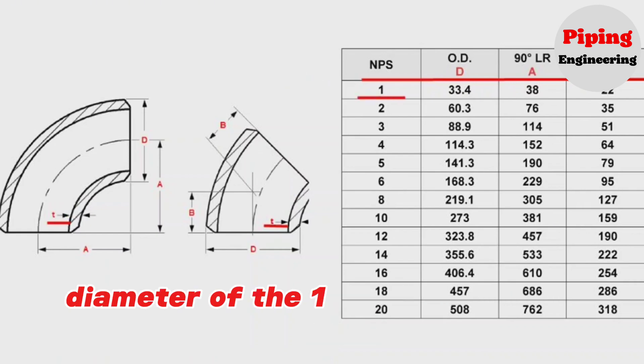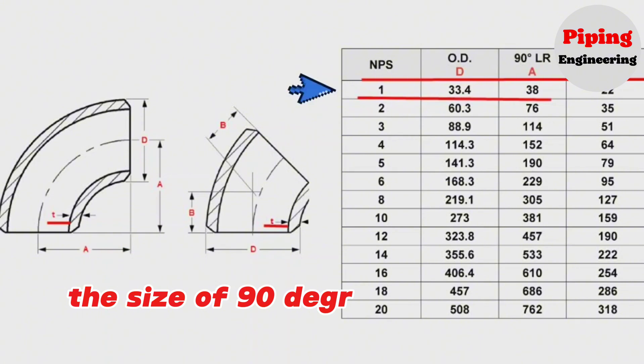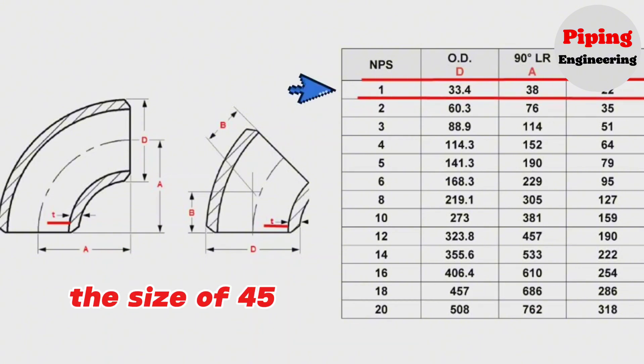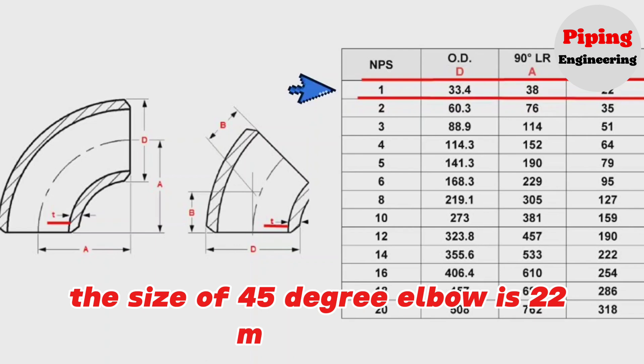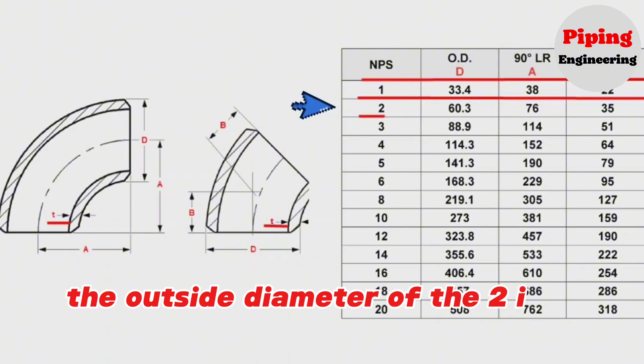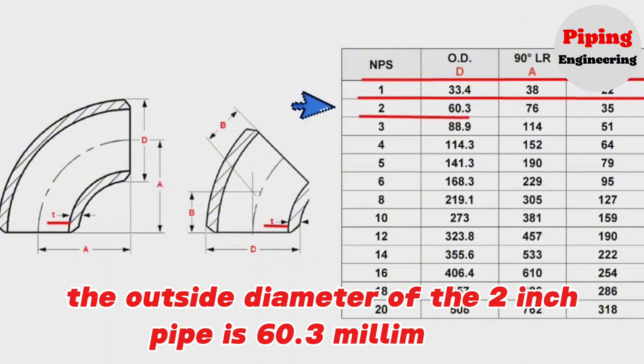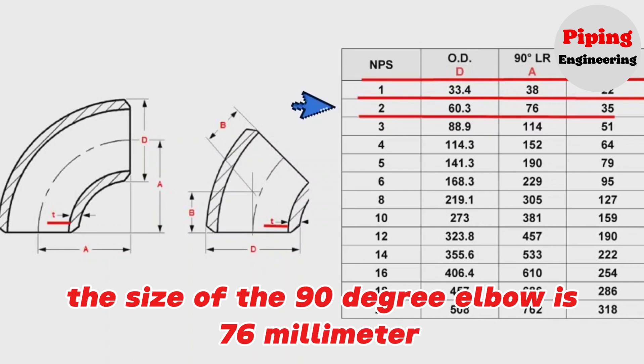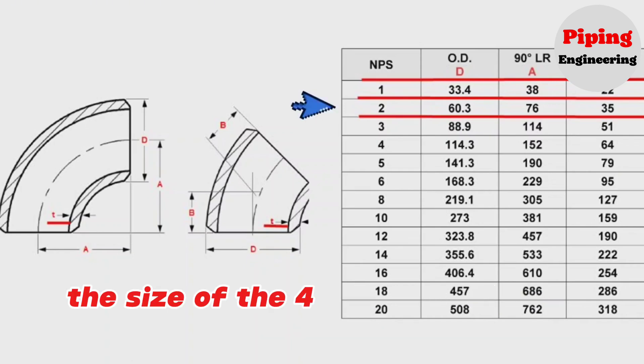We can see in the table that the outside diameter of the 1 inch pipe is 33.4 mm. The center-to-end size of the 90 degree elbow is 38.4 mm. The size of the 45 degree elbow is 22.4 mm. The outside diameter of the 2 inch pipe is 60.3 mm. The center-to-end size of the 90 degree elbow is 76 mm. The size of the 45 degree elbow is 35.4 mm.